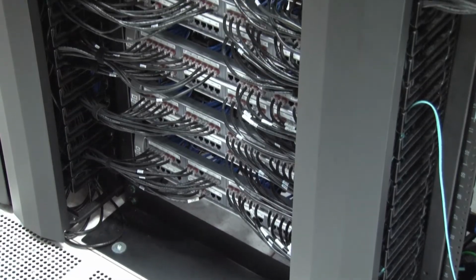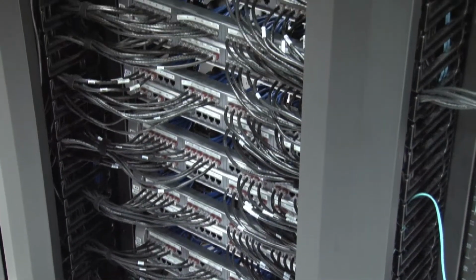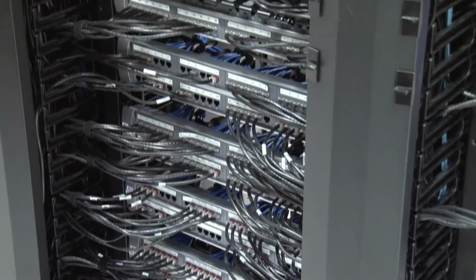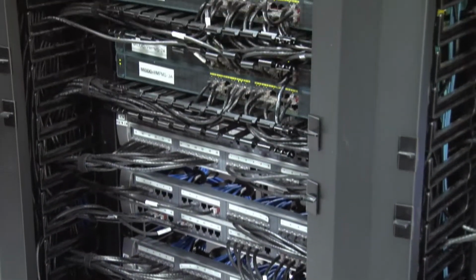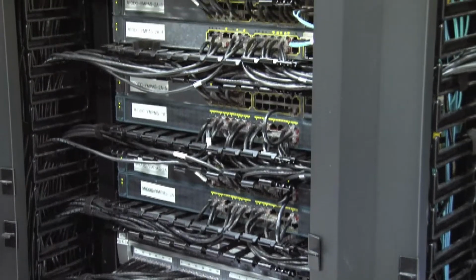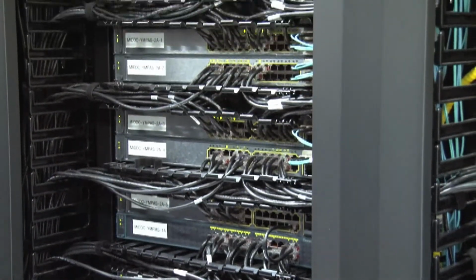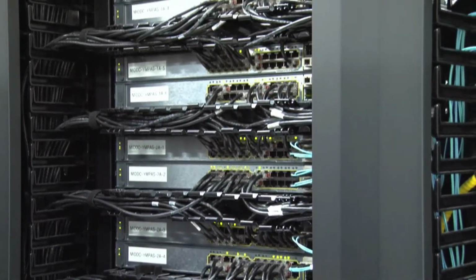For 20 amp branch circuits feeding to the power racks, we have a minimum size of 10 gauge wire that's above what code is demanding. The majority of our circuits on the raised floor are 30 amp circuits, also above and beyond code. We go with 8 gauge wire.